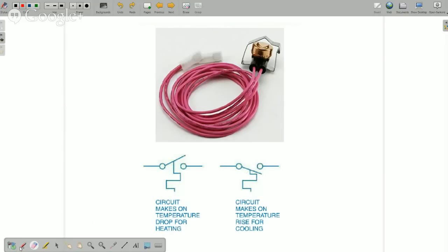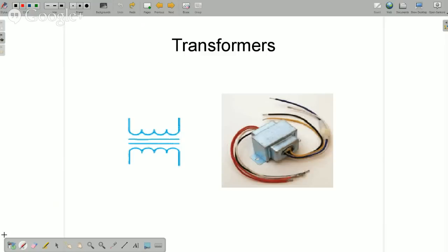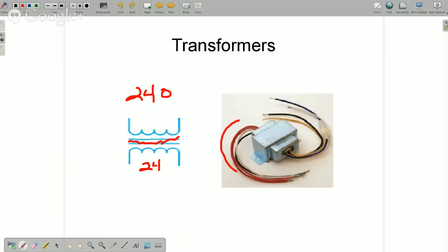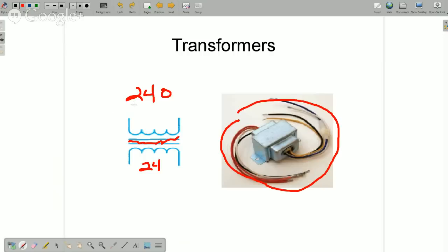No matter what type of switch it is, the bimetal symbol indicates a temperature-controlled switch. They're always shown in their normal position on the schematic, and you need to know the temperature at which they make and break. A transformer: this is where we take 240 volts in and drop it down to 24 volts for our control voltage. That is just about the universal symbol for a transformer. You may not always see the line in between, but these are in every piece of equipment. It's usually 240 volts in and 24 volts out, or 120 volts in on a gas furnace and 24 volts out.